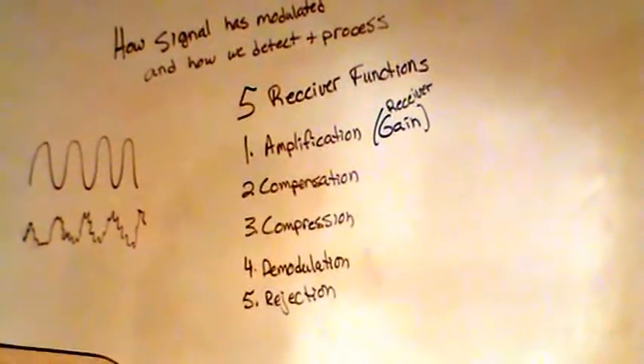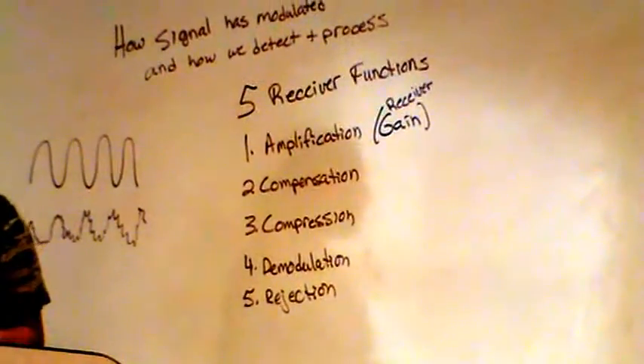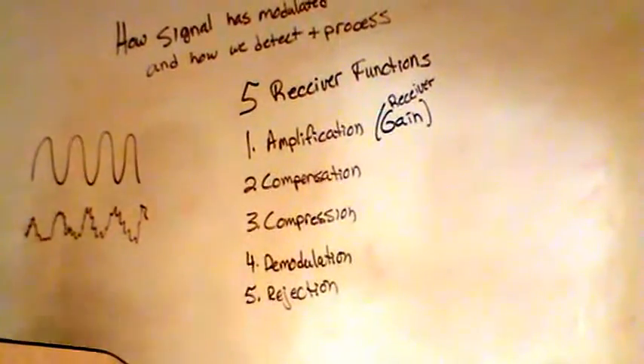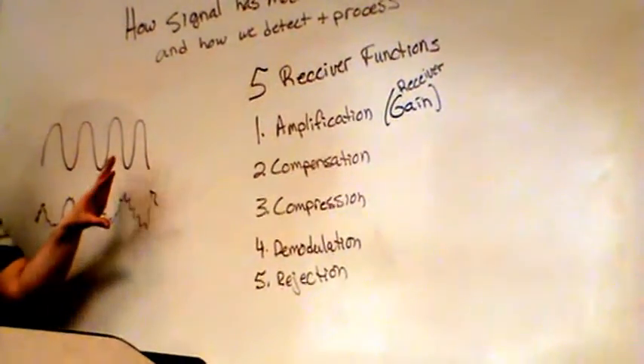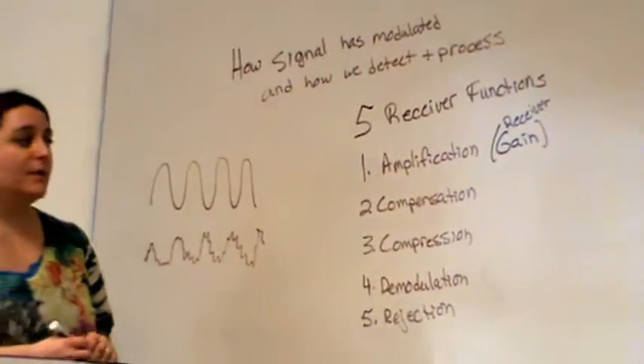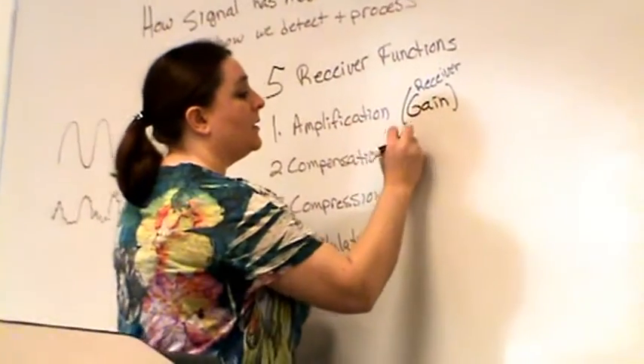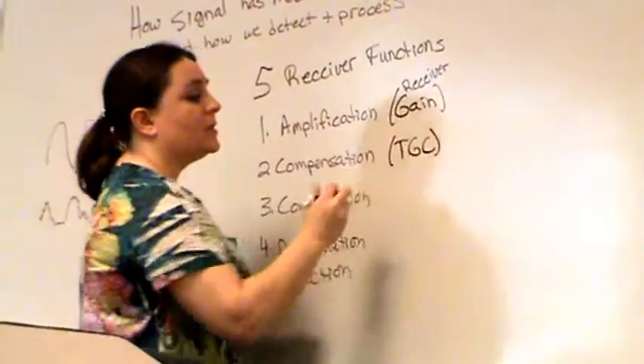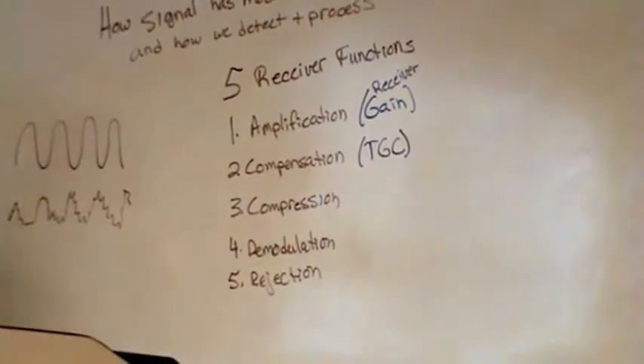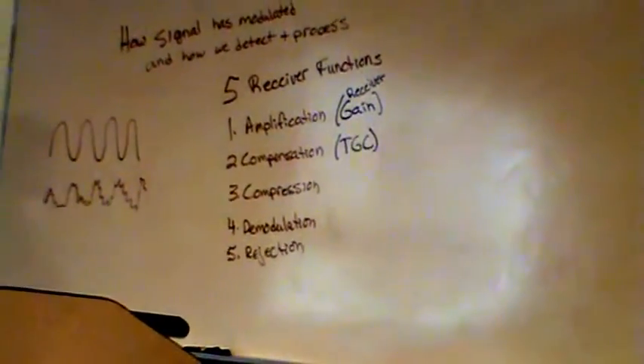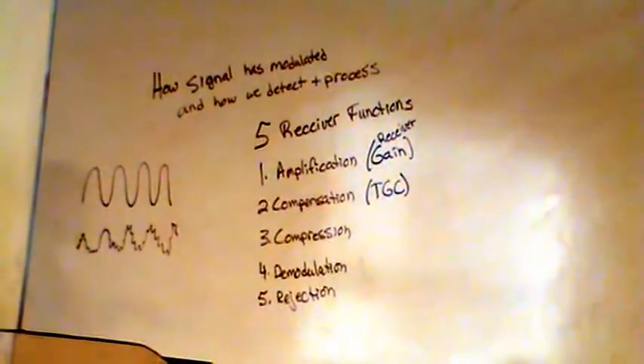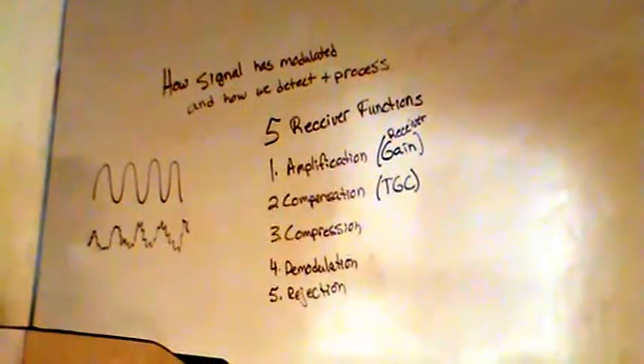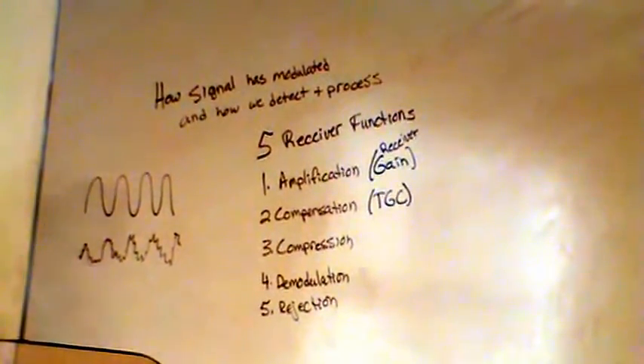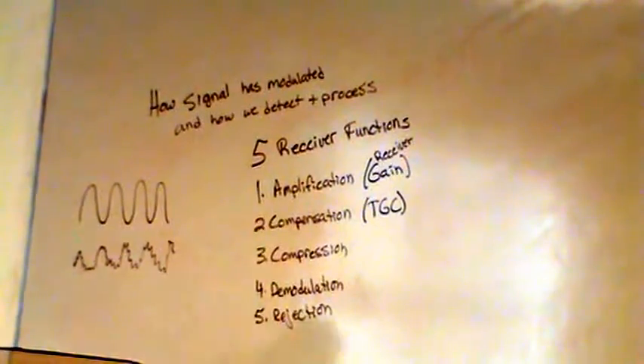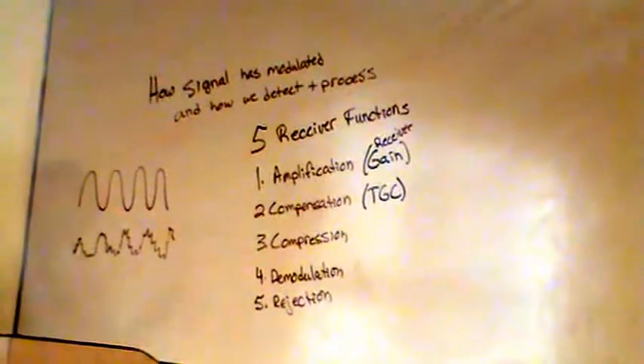So we do amplification, then we can do compensation. Compensation is increasing the amplitude of the echoes that came later in time. And again, there's some compensation that happens in the system automatically, and then we have further control of compensation by using the TGCs, time gain compensation, that's what that stands for. So I can continue to adjust that.